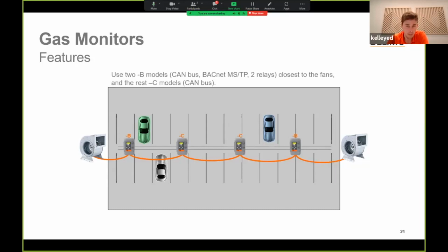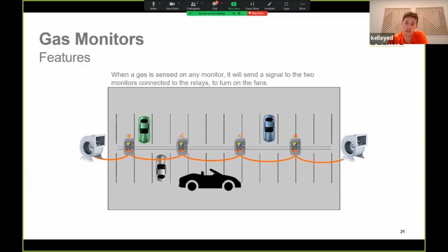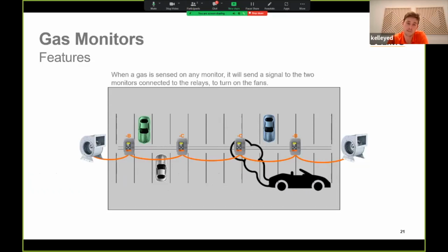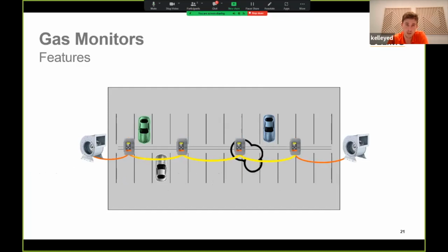So what will happen here is, if any of the gas monitors detect the gas, they'll send a signal to the B models that are physically connected to the fans to turn them on. And we say this will save money for 2 reasons. You only need to buy the analog outputs and relays that you're using for your system. And second, you don't need to purchase an additional designated controller because the gas monitors are the devices physically controlling the external equipment. So in this case, 2 exhaust fans.